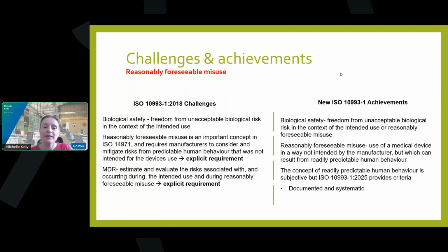It requires manufacturers to consider any reasonably foreseeable misuse, and they put that down to predictable human behavior, which is a huge ask. And I don't know about you, but for me, trying to predict human behavior is quite a difficult task, and sometimes requires you to have a looking glass or predict the future. So it's not necessarily a term that is easily understood. But the medical device regulations within Europe are also very explicit, and where you have intended use, you have reasonably foreseeable misuse. So whether we like it or not, it's a legal requirement. It's in the regulations. It's a requirement within 14971, which is one of the most important overarching documents across your whole process, be it biological evaluation, clinical, regulatory.